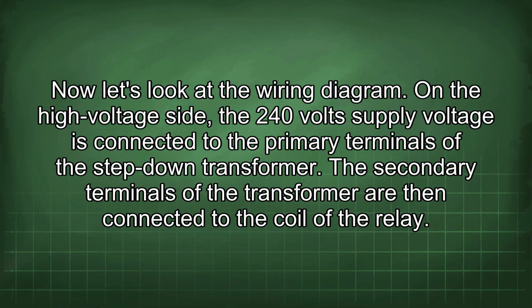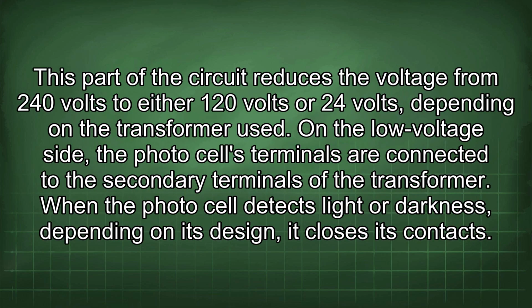Now let's look at the wiring diagram. On the high-voltage side, the 240 volt supply voltage is connected to the primary terminals of the step-down transformer. The secondary terminals of the transformer are then connected to the coil of the relay. This part of the circuit reduces the voltage from 240 volts to either 120 volts or 24 volts, depending on the transformer used. On the low voltage side, the photocell's terminals are connected to the secondary terminals of the transformer.